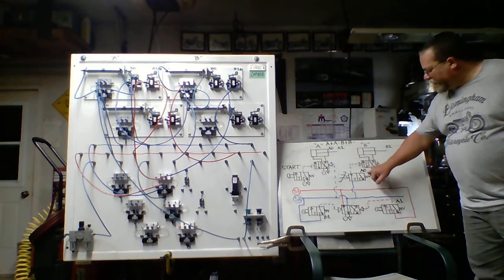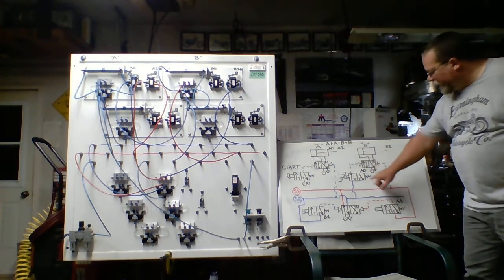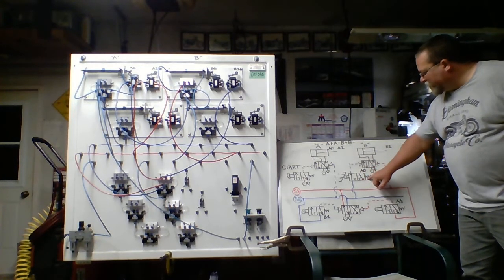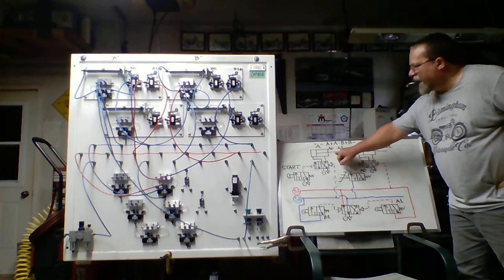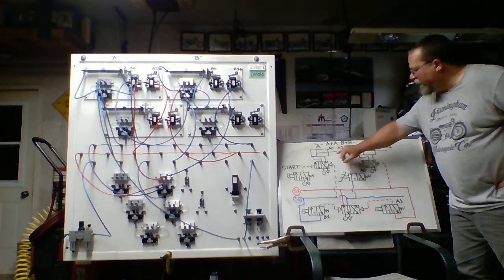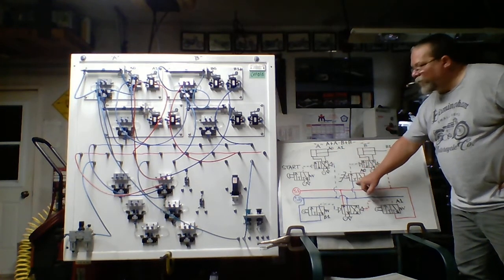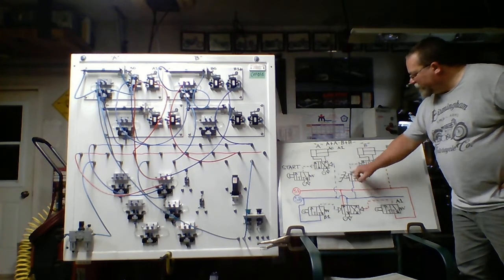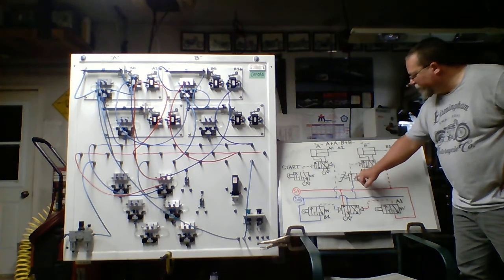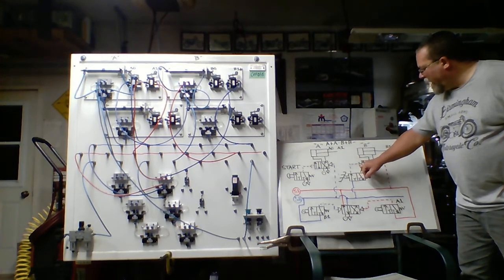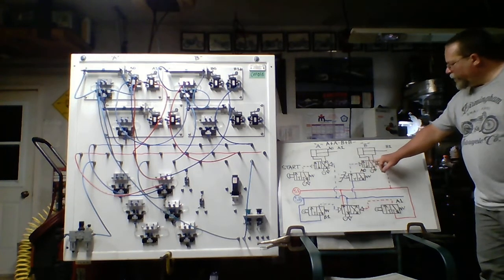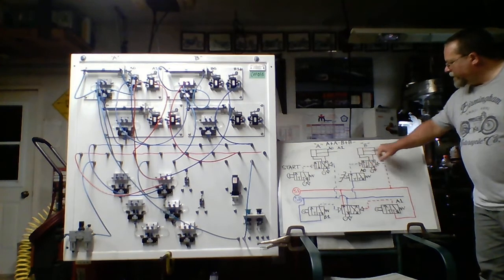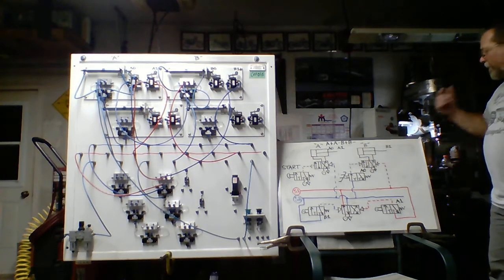Here's A0 as identified. And A0 is no different than A1. They're both 3-2s, normally closed, spring return. This, of course, is showing it's held open because when this is static, when I mean by static, when the whole circuit is idle, ready to go, this 3-2 will be pushed into an open position or shifted. So at this point in time, source 2 has energy. It flows through A0 because, of course, A is retracted. It's going to come over and pilot my 4-2, which controls B. Of course, the 4-2 shifts, opening the flow path to the blind end of the cylinder. The cylinder will advance. And when it advances, it's on B1.